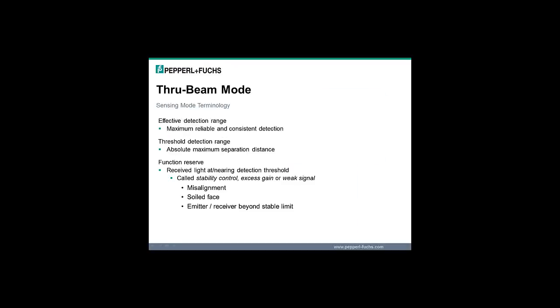Terminology used with through beam sensors: effective detection range is the maximum emitter-receiver separation distance for reliable and consistent detection. Threshold detection range is the absolute maximum emitter-receiver separation distance. Function reserve indicates when the light level at the receiver is at or nearing the detection threshold — commonly referred to as stability control, excess gain, or weak signal. This can indicate misalignment, a soiled optical face, or that the emitter-receiver distance is beyond the stable limit.